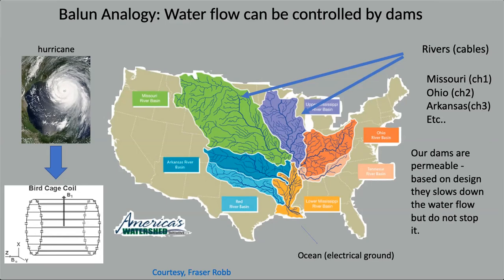This would generate high currents unless baluns are applied. A commercial 64-channel coil could sometimes have more than 100 of these traps within the coil in order to block these types of currents - pretty much on every cable, and sometimes a few on a single cable.